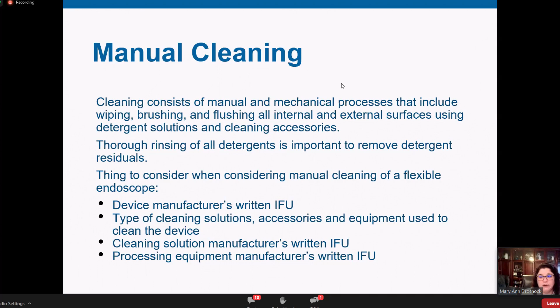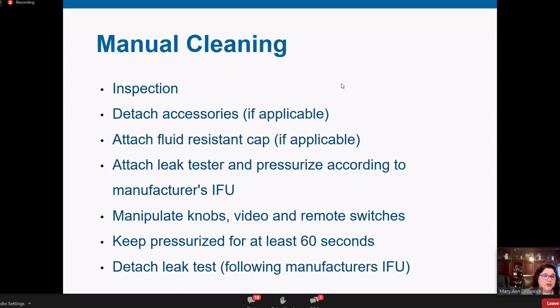As I said, lots of steps within manual cleaning, and we didn't change any of these per se, just went through and made sure they were adequate, follow the IFUs, making sure that you're doing everything appropriately, and following your instructions for your leak test also per the IFU, just upping that time to 60 seconds instead of 30 seconds.